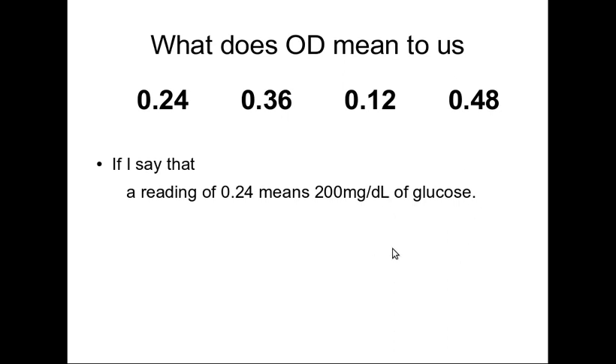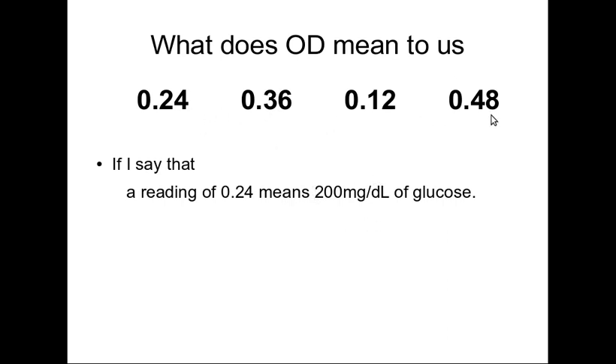Rephrasing this: if I use a solution whose concentration I know, test it, and find its optical density — for example, a solution of 200 mg/dL gives an OD of 0.24 — then I know that OD for that concentration, and I can find the concentrations of all other solutions. A solution whose concentration I know and which I use to analyze other solutions is called a standard or a calibrator.